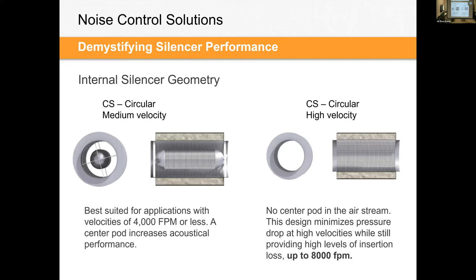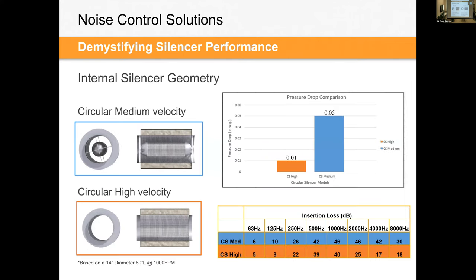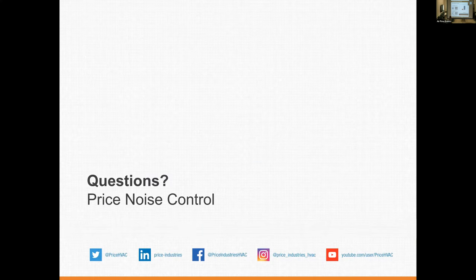I won't get into all the details on circular, but we do the same stuff with circular silencers where the center body will grow and shrink. The length can be adjusted, the acoustic media. There are packless circular options available. The same parameters sort of apply where you're balancing insertion loss and pressure drop. The more sound you want to take out, typically the more pressure drop you're going to have to deal with.